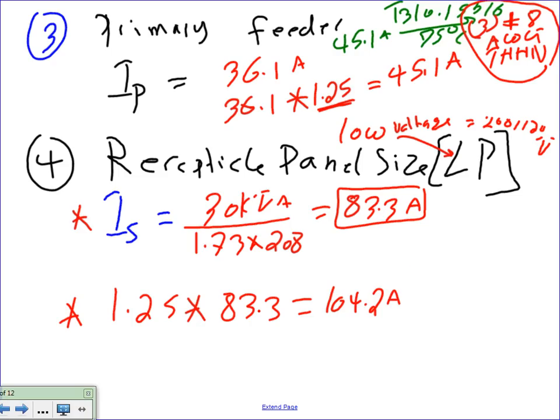104.2 amps. Thank you, Oladipo. Okay. Why did I multiply by 1.25, Chris? I would like to assume that my panel, after I installed it, can be used fully to the 83.3 amps. But if it's used fully to the 83.3 amps, you have to allow continuous load of 25% extra there.